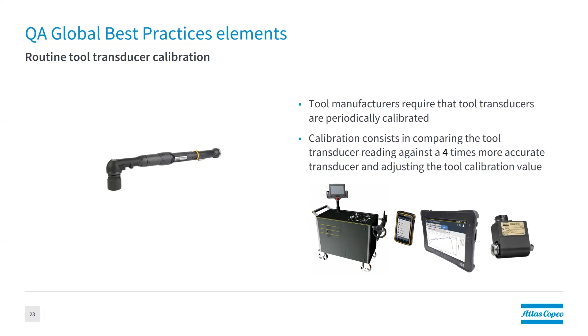On the other hand, remember the other transducers in that picture - those are all the transducers in our plant standards, meaning all the transducers you need for quality assurance. These are already more accurate than the ones on the tool, and they need to be maintained at the correct level of accuracy, which also requires calibration.